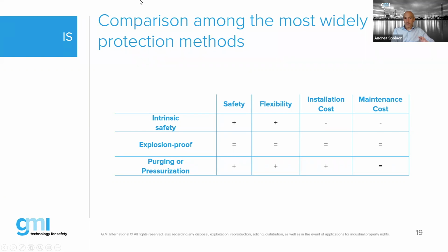So I would give you just this information about the different protection methods we mentioned: explosion-proof, intrinsic safety, and pressurization. Given that explosion-proof is safe and flexible, it has some installation cost values and some maintenance cost. From this point of view, we would say that purging is more safe, more flexible, costs more at the level of installation, and has more or less the same maintenance cost.